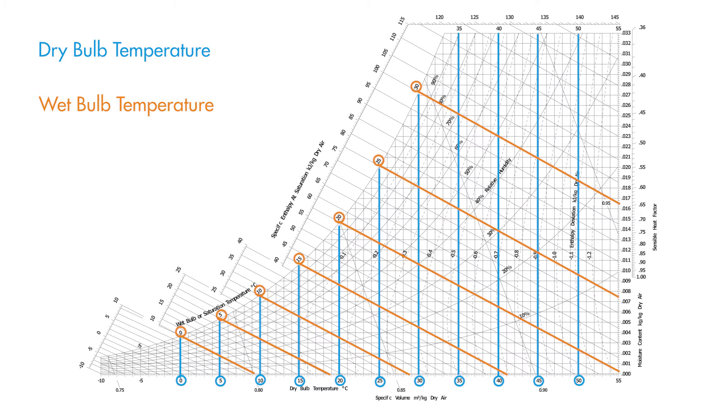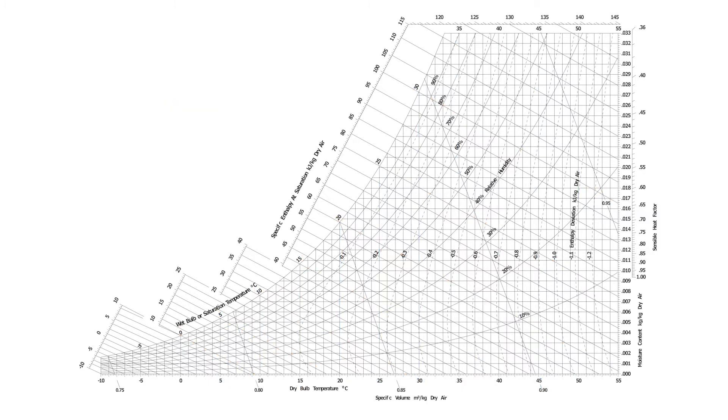These orange lines represent wet bulb temperature. Wet bulb temperature is the temperature you would read on a thermometer that is wrapped in a wet cloth and with air blowing over it. Any difference between the dry bulb and wet bulb readings is caused by the cooling effect of evaporation on the wet bulb thermometer.